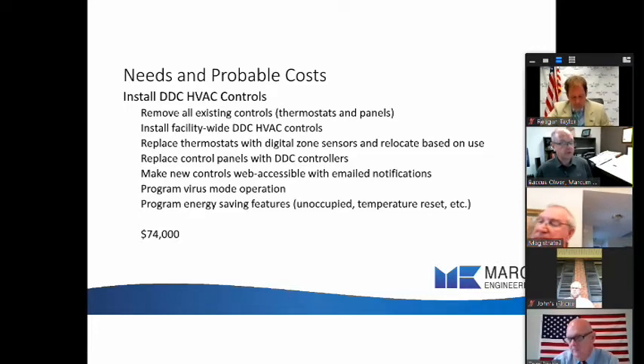We would have an unoccupied mode. We'd have temperature resets for mild days. There's many things we can do to improve the efficiency of the building if we had a computerized control system. These aren't cheap. You'll see that that's $74,000 to go in there and integrate all that in and program it.